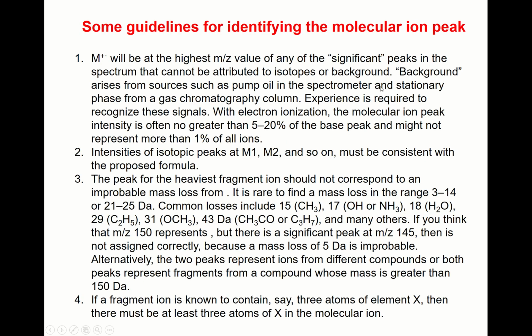And background arises from sources such as pump oil in the spectrometer and the stationary phase from a gas chromatography column. Experience is required to recognize these signals. Okay, background also contributes to the mass spectrum. So you have to be well trained to distinguish. Okay, is this from the background or not. Okay, so experience is required, right?